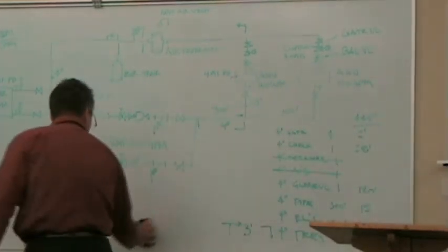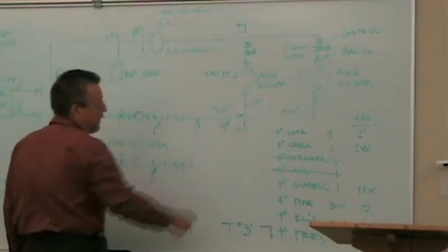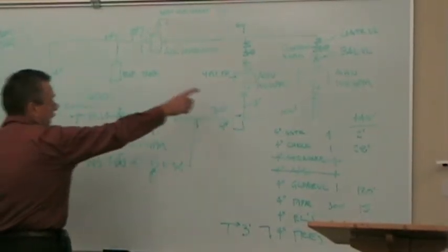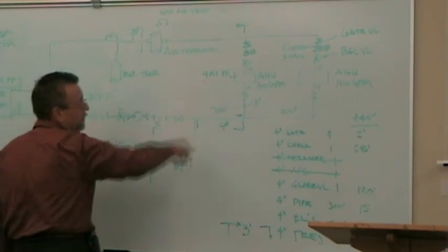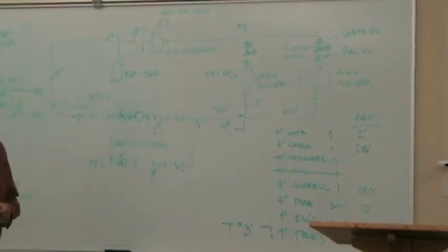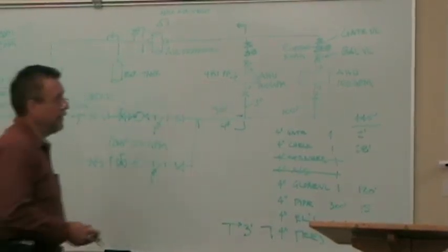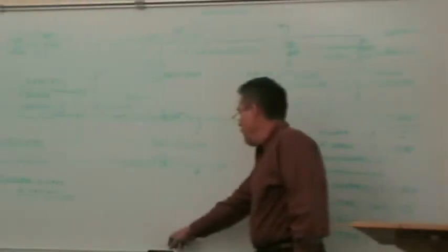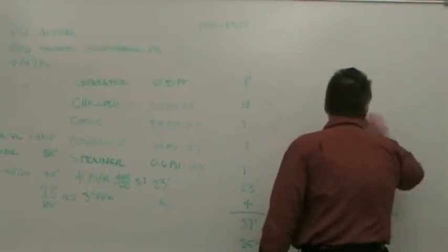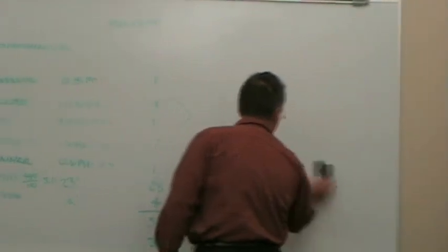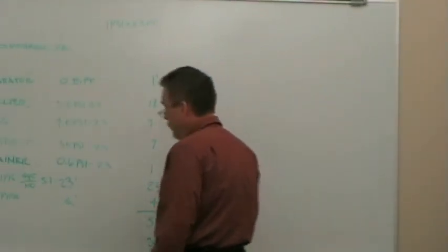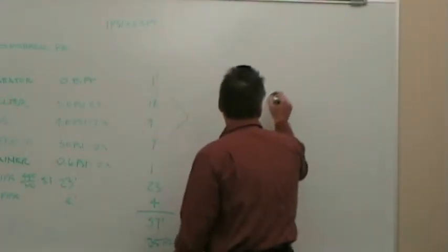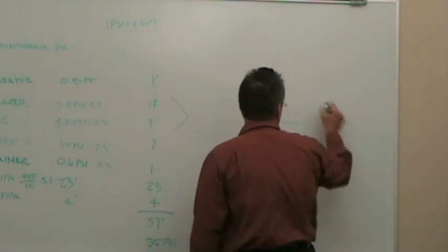Same piping system. This could be the chiller, this could be the cooling tower. So I'm pumping out of the cooling tower into the chiller, back to the system. But a cooling tower generally is an open piping system. So what's different right here at the cooling tower? I've got similar flows, similar type fittings, similar chiller barrel, so it's going to have a very similar calculation. But now I got this cooling tower sitting out here.